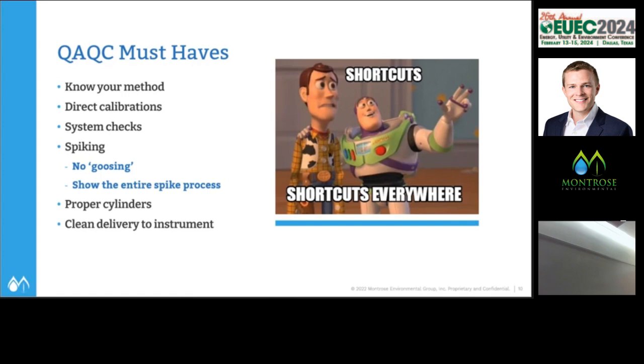So now diving into QA/QC, quality assurance, quality control. In FTIR world, we generally follow EPA method 320. Thousands and thousands of tests done with it. We also follow ASTM D6348-12, and there's a revision coming out to that soon. But we have to do certain things to make sure that the system's working right as a tester, right? We have to send direct gases to the analyzer through the system. We have to do an analyte spike. Pretty stringent stuff to make sure things are well.